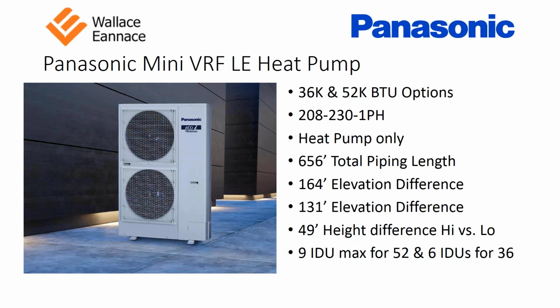Okay, Panasonic Mini VRF LE heat pump system. So this is our first offering of our VRF lineup. This is our 208, 230 volt single phase unit. We offer it in 3 ton and 4.5 ton, 36,000 and 52,000 BTU options. It is a heat pump only. The total piping length that we can connect to this system is 656 feet.